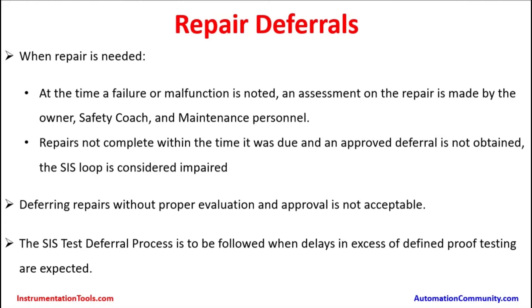When repair is needed: at the time a failure or malfunction is noted, an assessment is made by the owner, safety coach, and maintenance personnel. Repairs not completed within the time due where an approved deferral is not obtained cause the SIS loop to be considered impaired. If the instrument continues to function but proof testing is not done per the planned schedule and repairs are not attended to, that particular loop becomes impaired. Deferring repairs without proper evaluation and approval is not acceptable.